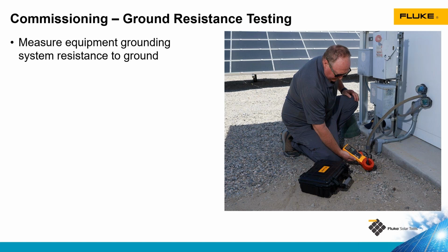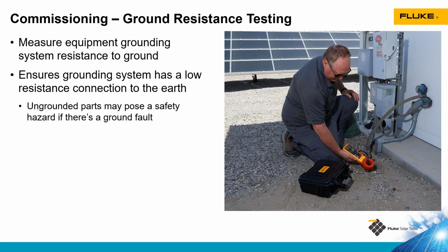A related test is ground resistance testing, and this is measuring to make sure that our ground rod or grounding electrode conductor or grounding electrode is properly connected to the actual physical earth. If there's not a good connection, we have the same problem we had in the last test where it becomes a safety hazard, and overcurrent protection devices may not work properly.